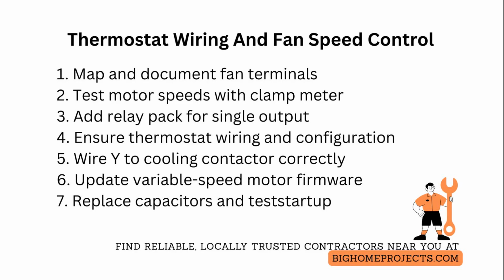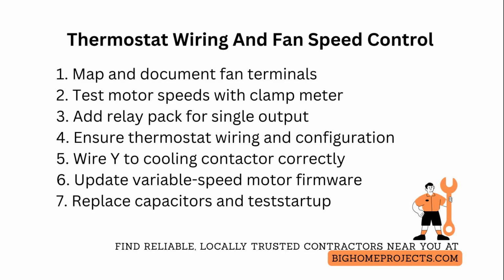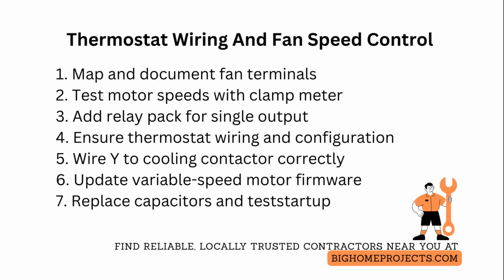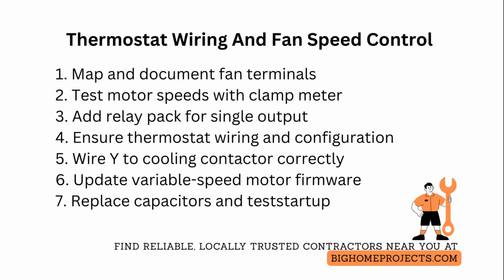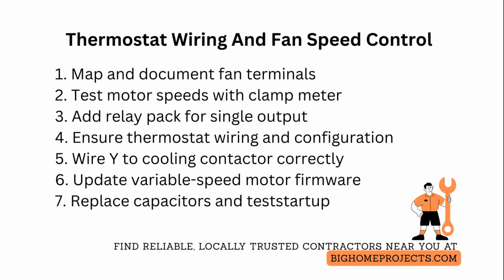If your system uses a 2-stage compressor, confirm which Y terminal corresponds to first stage and second stage cooling to avoid mismatched blower speeds. If the furnace uses a variable speed motor with a control harness, update the motor control module firmware and set the comfort versus efficiency curves according to the installer instructions, because factory defaults often bias efficiency and can underdeliver comfort during heating.